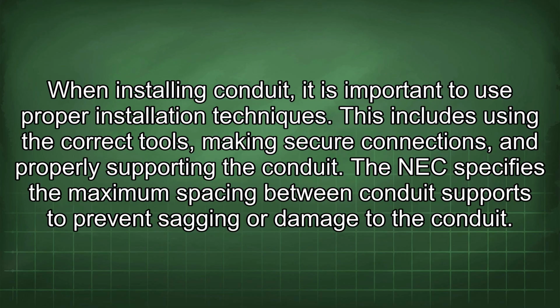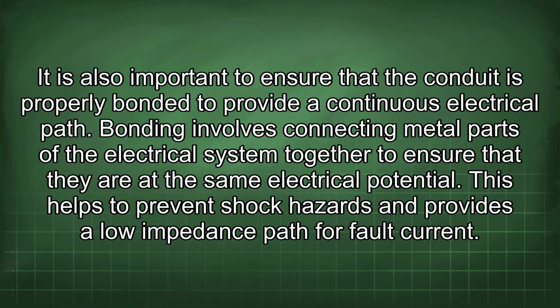When installing conduit, it is important to use proper installation techniques. This includes using the correct tools, making secure connections, and properly supporting the conduit. The NEC specifies the maximum spacing between conduit supports to prevent sagging or damage to the conduit. It is also important to ensure that the conduit is properly bonded to provide a continuous electrical path. Bonding involves connecting metal parts of the electrical system together to ensure that they are at the same electrical potential. This helps to prevent shock hazards and provides a low impedance path for fault current.